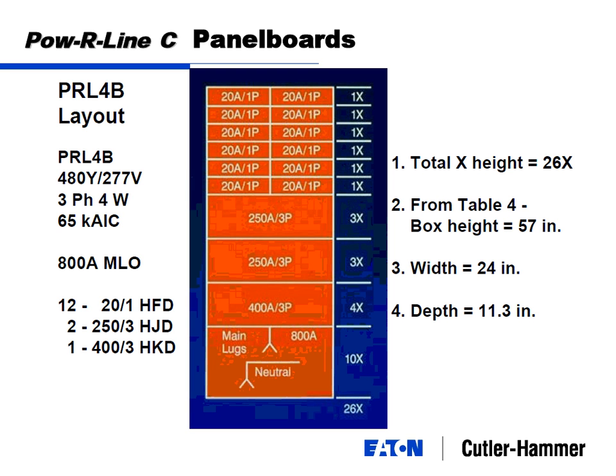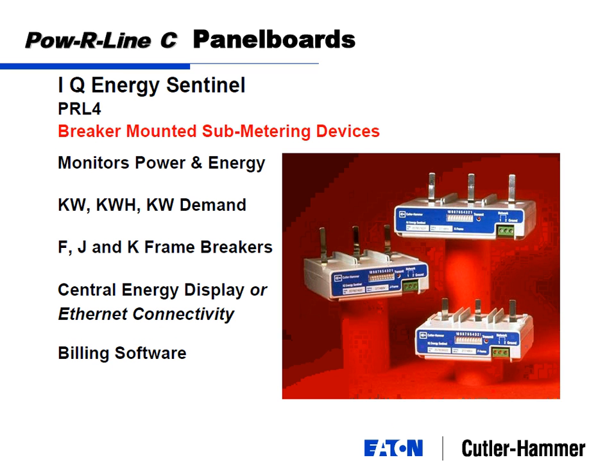What it comes down to is, on a normal circuit breaker, one pole is 1 3/8 inch. So 1, 2, 3 poles is 1x, 2x, 3x. So it translates trying to go, okay, I've got a breaker that's 4 3/8 inch high, and how many of those can I fit in the panel board? It's a way to translate that to, okay, I've got 26x worth of panel with breakers. How much can I fit in here? 50x. Everything works. So that's the gist behind that.